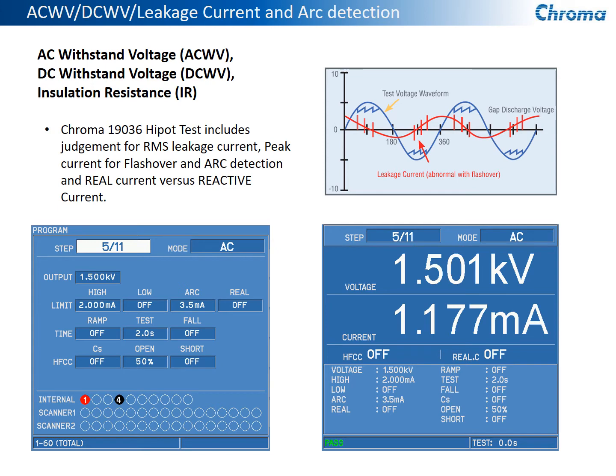So the AC withstand test that we perform, we can program it manually on the front of the unit. We also, of course, have software available. But what I'm showing here on the left is the actual display capture on the unit for setting up a program step for an AC high-pot test. You can see that in addition to giving us the voltage and the high and low limit settings, we can also do the arc detection, but we have one other feature called real. This is real current versus reactive current, and we can also use that as a measurement and set a threshold for that as well. The test can be set for a ramp up, a dwell time or test time, and a falling edge time.